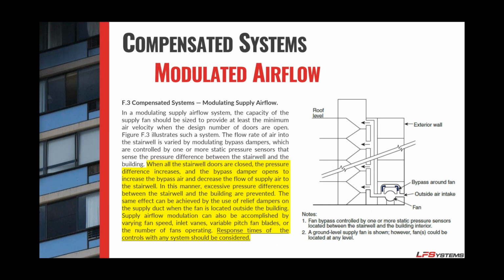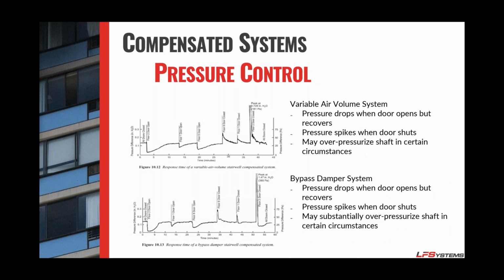And this is a diagram showing really 2 options. One is if you put a fan directly into either your lobby, again, it's showing stairwells, but the principles still apply. You can do a bypass system for stairwells. The problem with elevators is because they're so much tighter of a window, you're just not going to be able to eliminate those spikes with the bypass damper system.